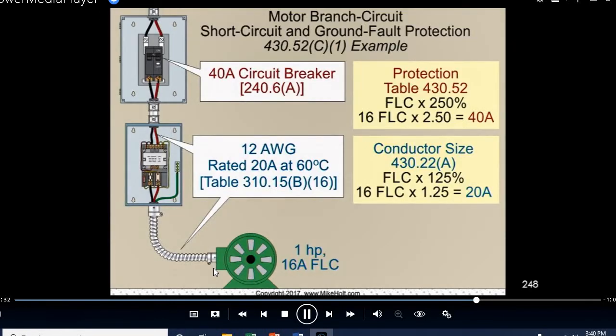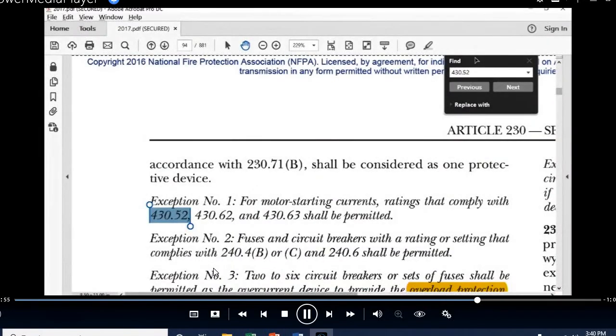Here we go. 1 horsepower motor. We've already determined it draws 16 amps. We size the wire at 125%. That was 20 amps. We then go to the code book at 60 degrees C, 12 gauge wire. So we're good there. The breaker is sized at 250% because we go to the table, 430.52, 52C.